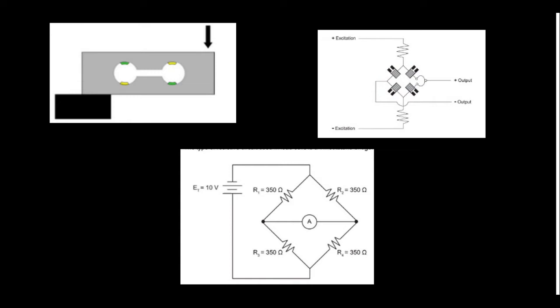Out of these four strain gauges, two are for compressive force, and two are for tensile force. Whatever strain gauge is shown here is of 350 ohms. 350 ohm is the resistance when there is no weight placed on the load cell. For this particular configuration, 350 ohm is the strain gauge resistance; it can also be 120 ohms. Now, what happens?